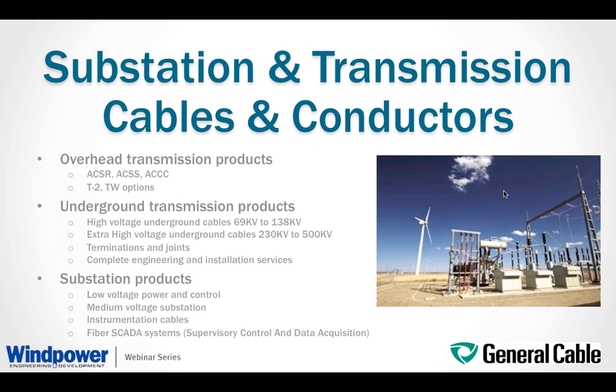And then for transmission products, these can be either overhead or underground insulated cables. There are a number of different overhead conductor designs available, ranging from ACSR, aluminum conductor steel reinforced, or ACSS, aluminum conductor steel supported using soft annealed aluminum wires, providing improved thermal capabilities. Other products such as ACCC, aluminum conductor composite core, or T2 twisted pairs, or trapezoidal wire designs can also be used.